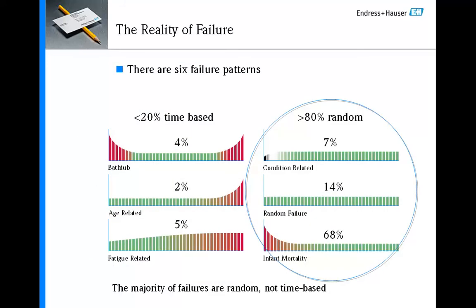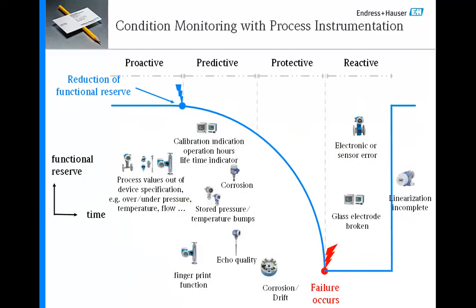This confirms Shell's findings that proactively accessing a field device to check its status more often than not resulted in no action required. This is why the Endress+Hauser PAM software tools has incorporated a performance monitoring module. The PAM suite continuously monitors the health and performance of the field devices, reporting to maintenance teams when the performance or health status of a field device has changed and human intervention is required.